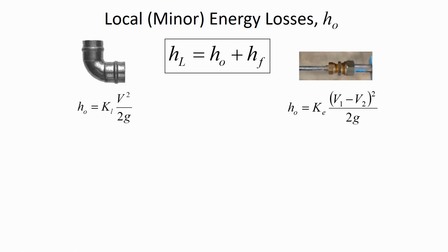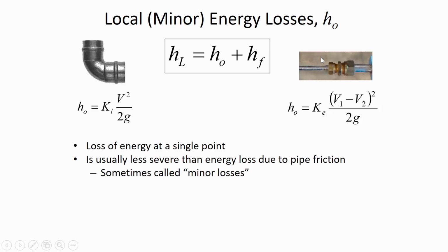And so you have to be sensitive to the table that you're using and look at, is the K value calibrated to the difference in velocity, or is the K value that they've provided in this table related to an inlet or an outlet velocity. Last semester in the lab, the K values that I gave you were specific to an inlet or an outlet velocity.